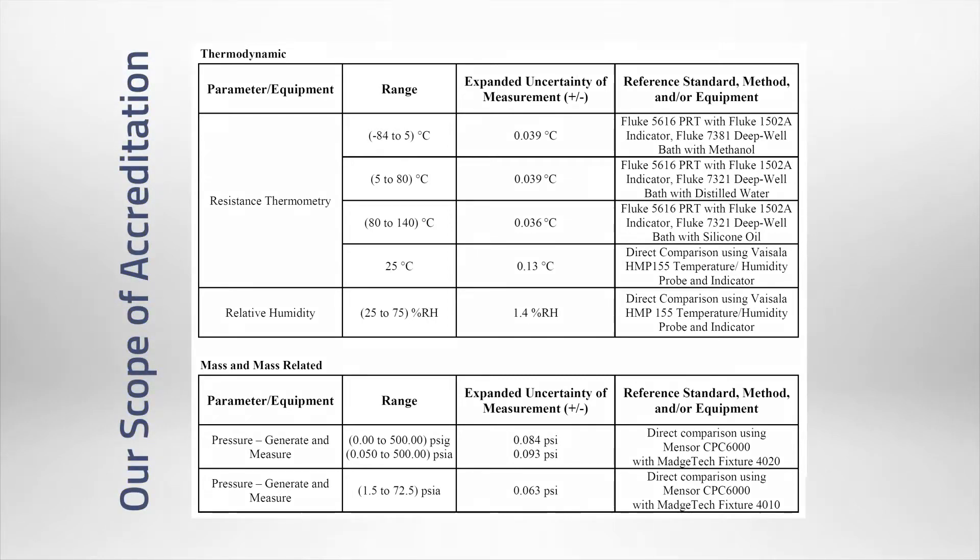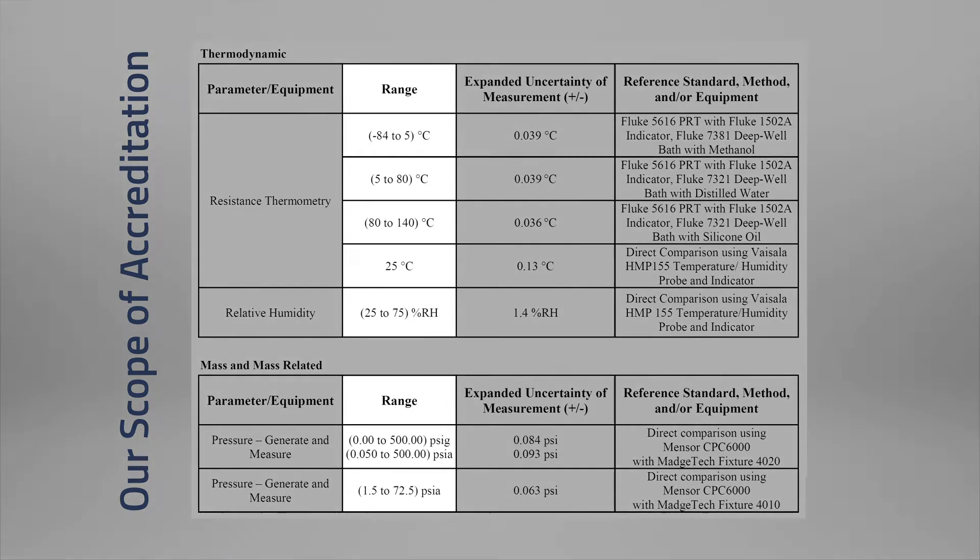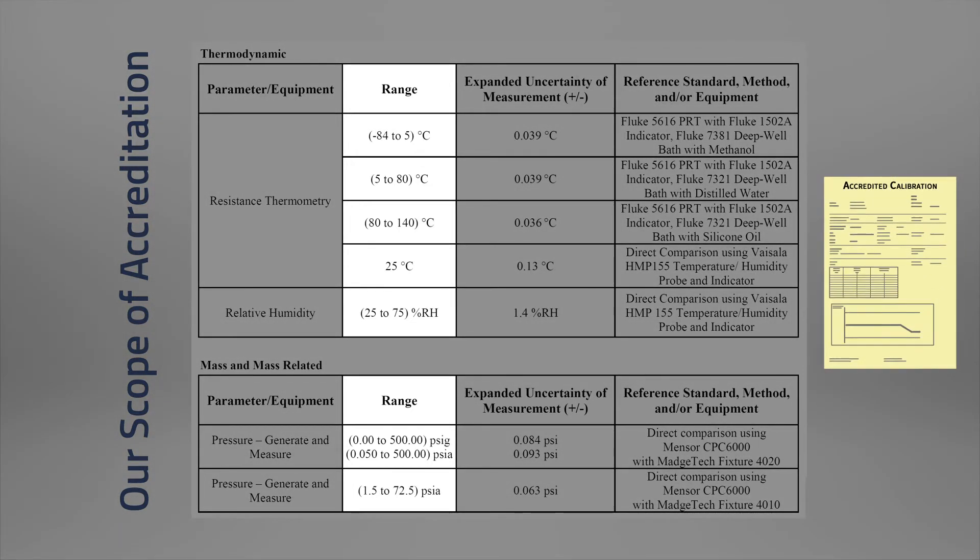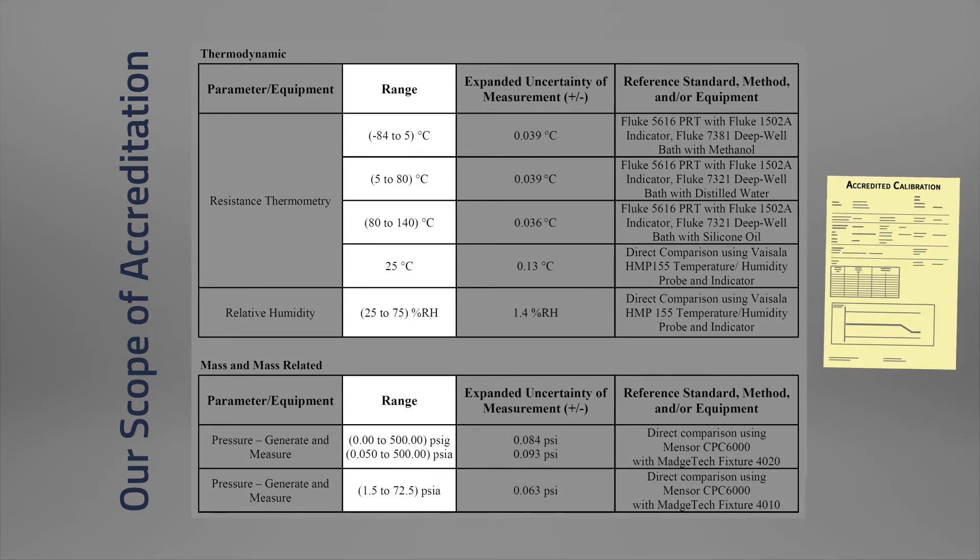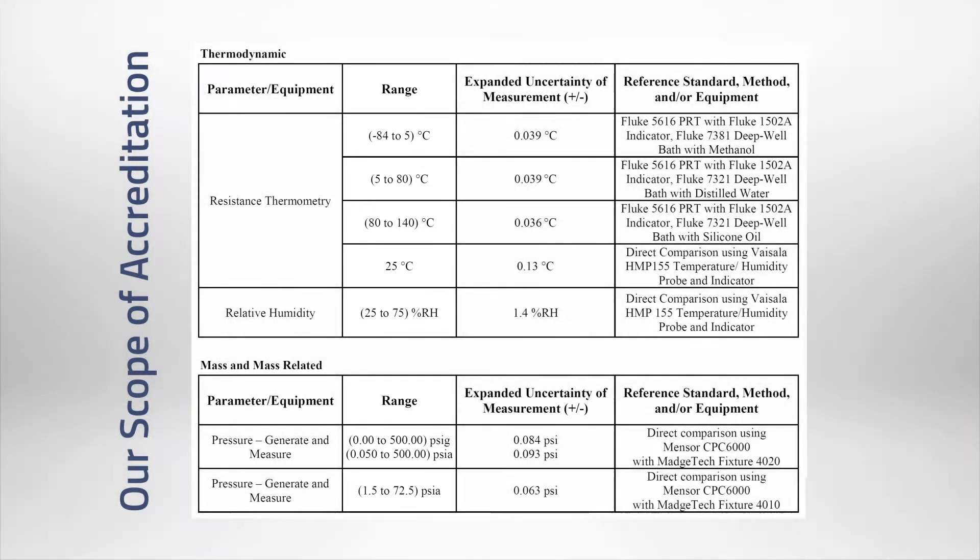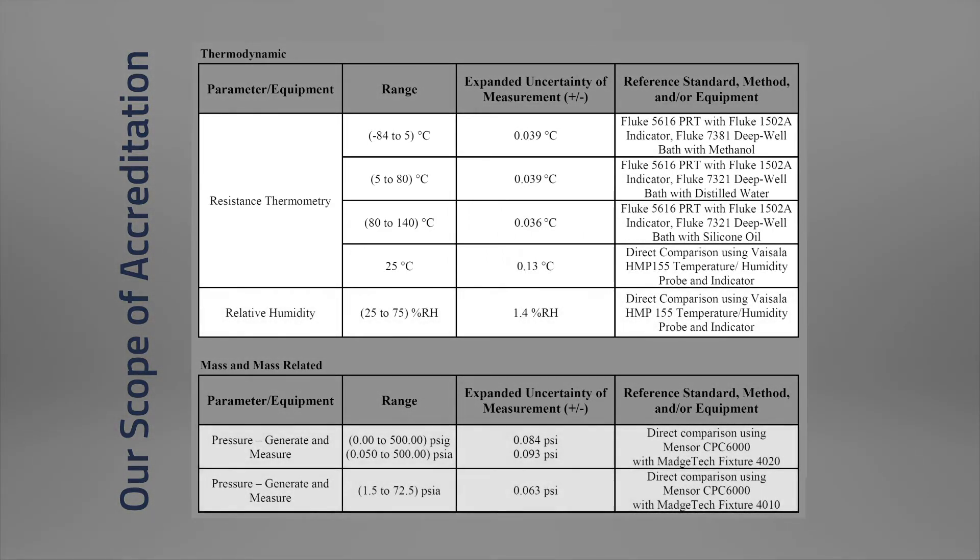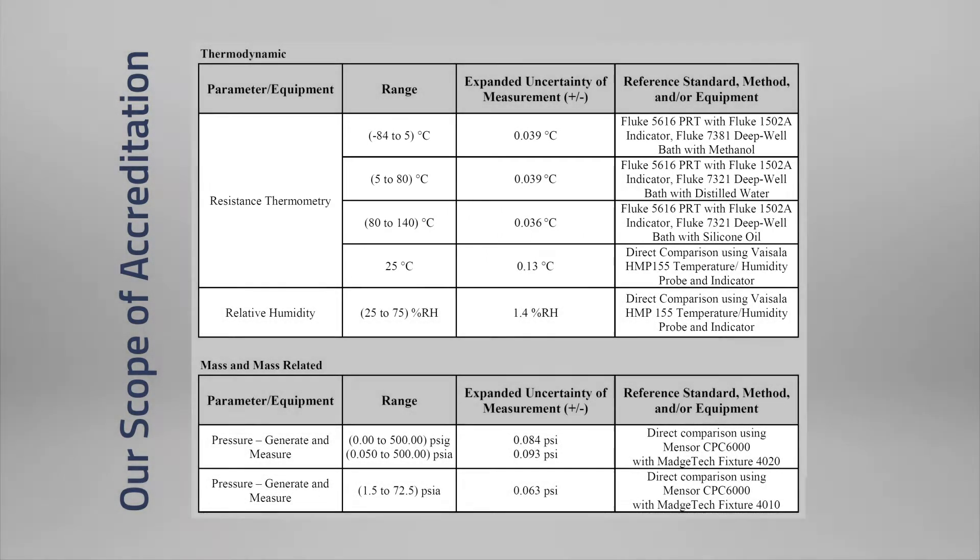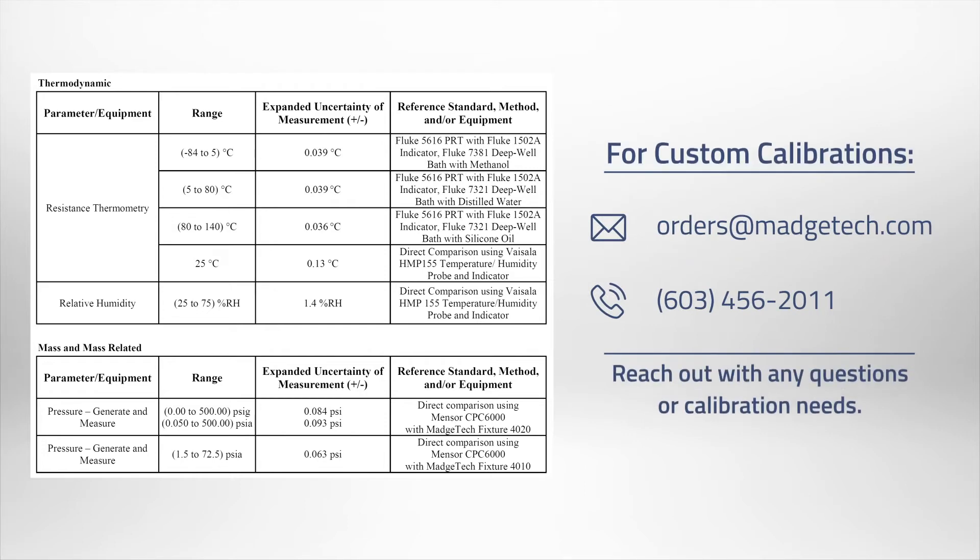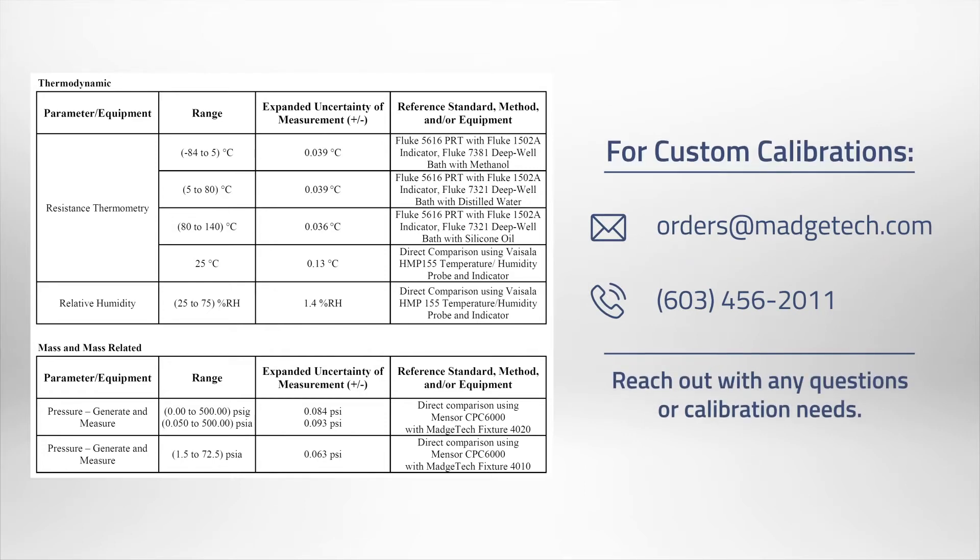Calibrations for these parameters that are calibrated within the value limits will receive an accredited certification. Accredited parameters include temperature, humidity, and pressure. Accredited calibrations can also be custom-ordered so long as the points fall within our scope.